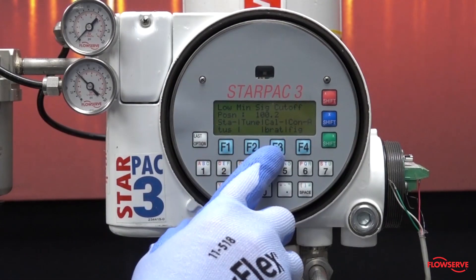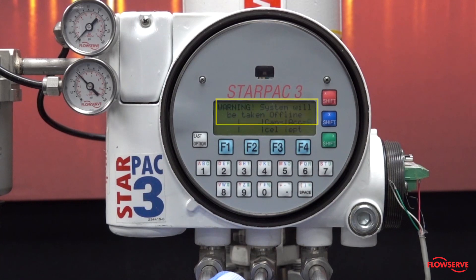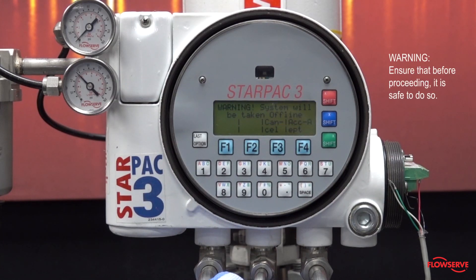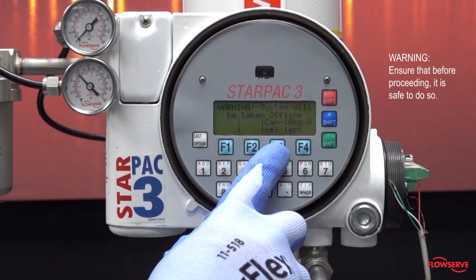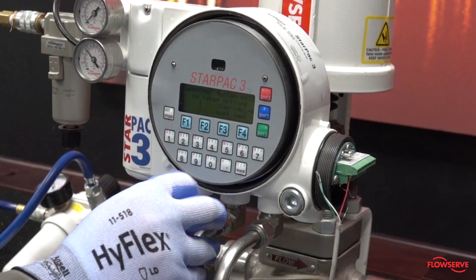Now select the F3 button to start a calibration. The system provides a warning that the StarPac will now be taken offline. Be sure that before proceeding it is safe to do so. During the calibration the valve will move, and therefore it is critical to ensure process isolations are in place before proceeding.